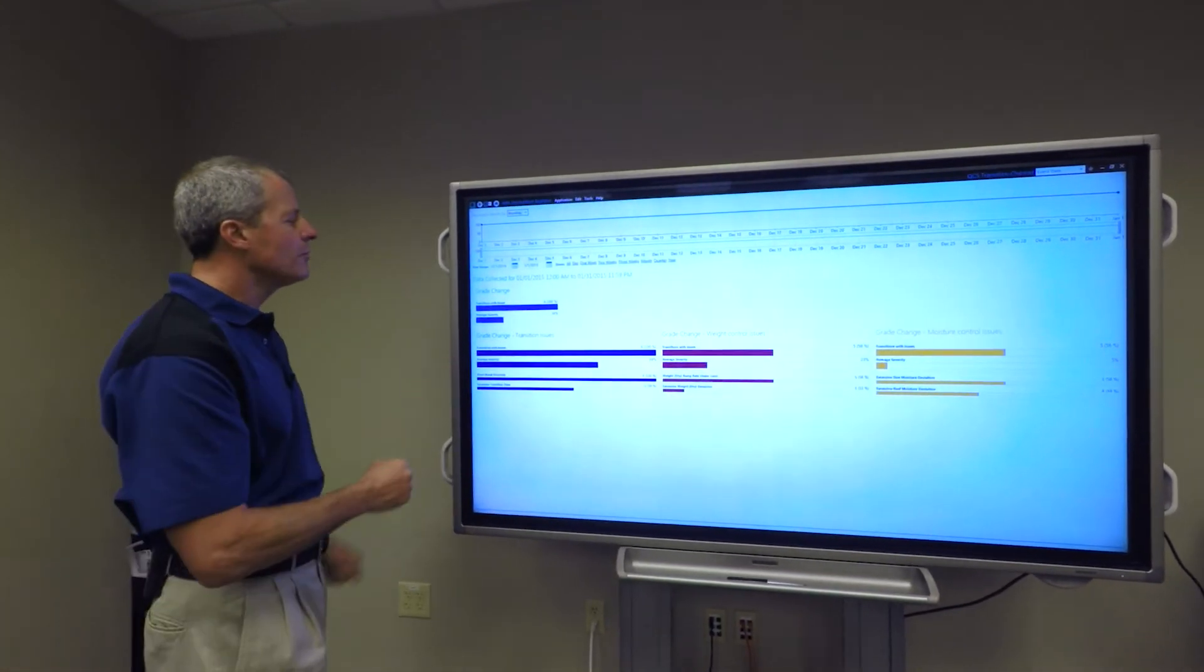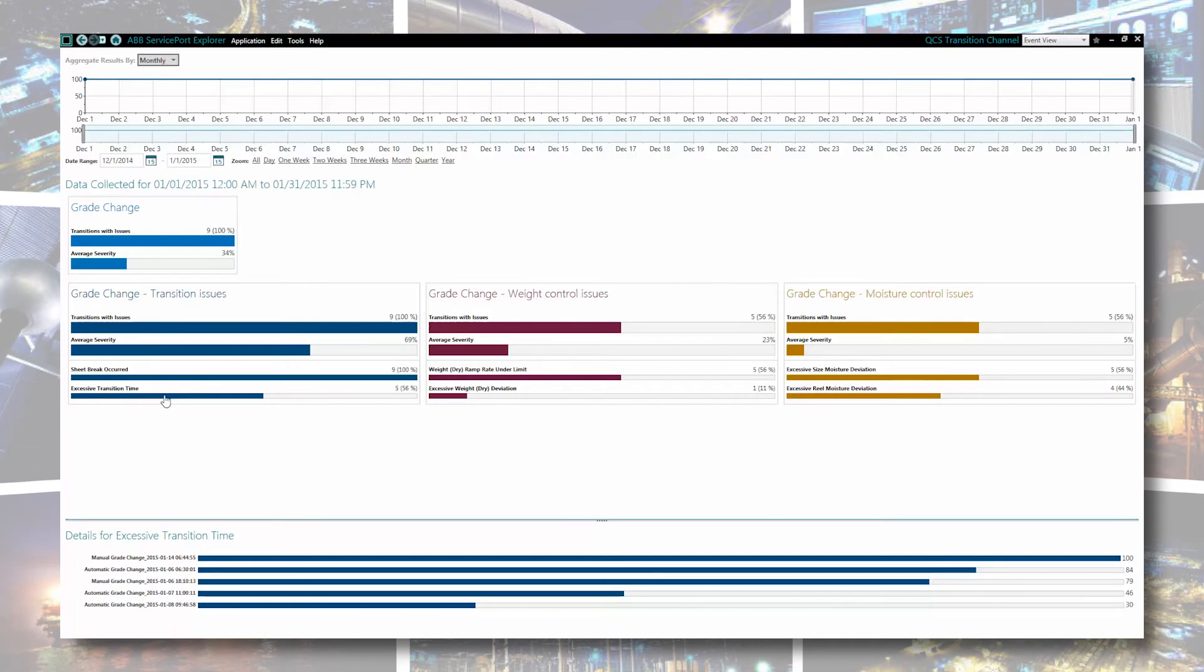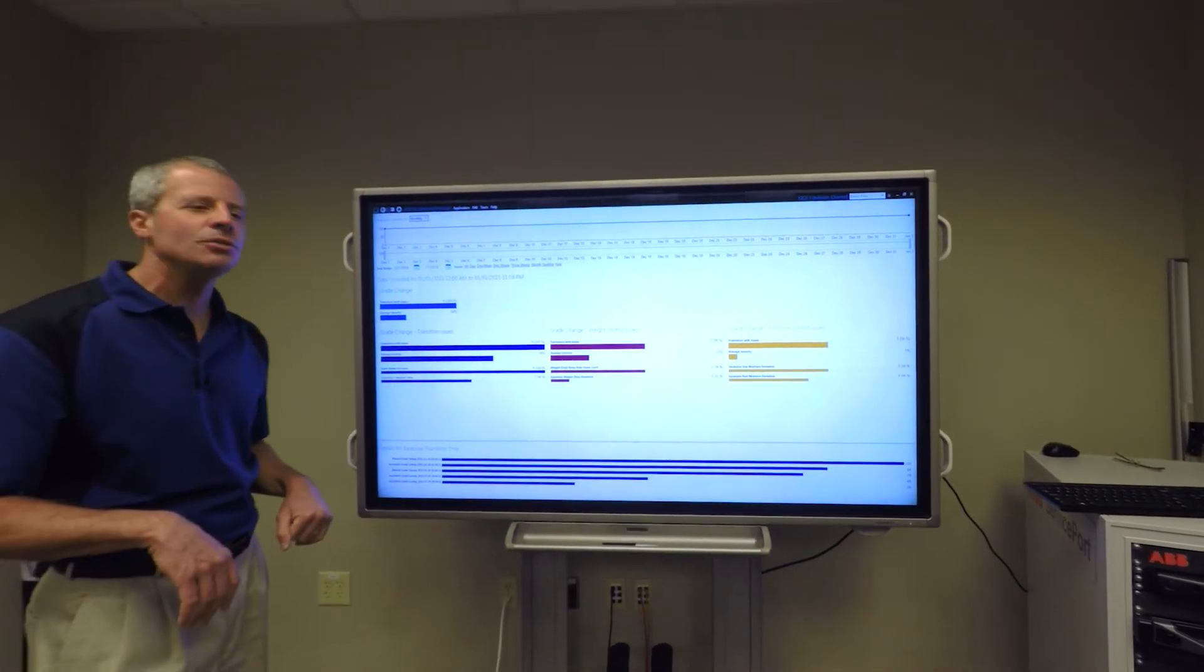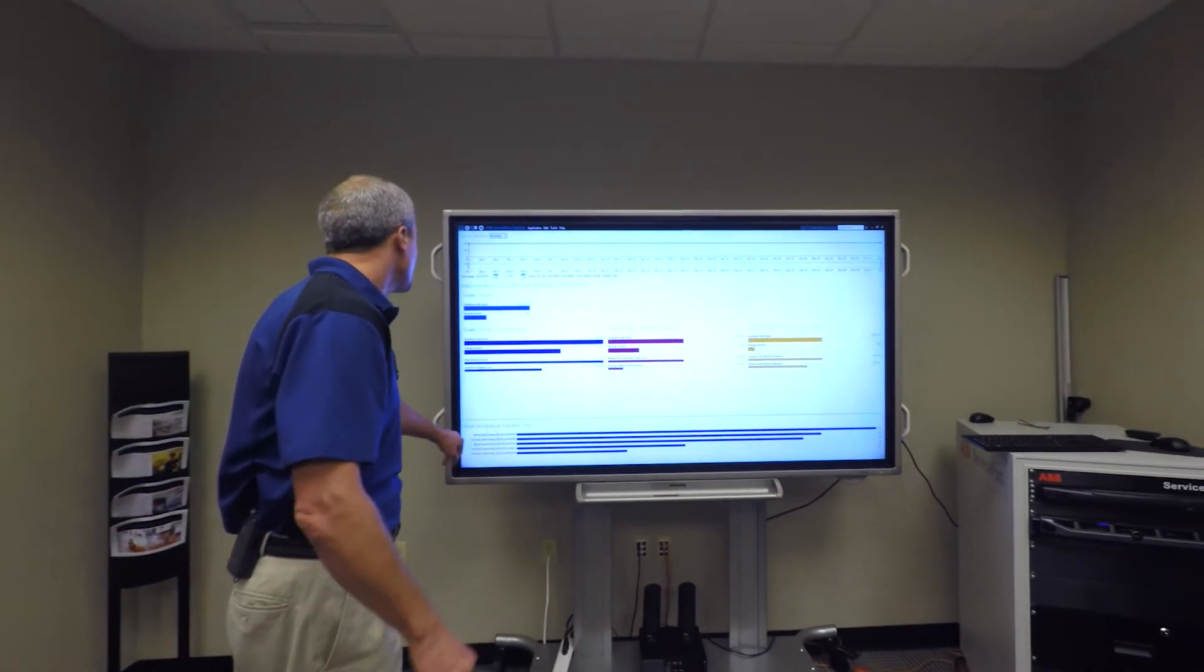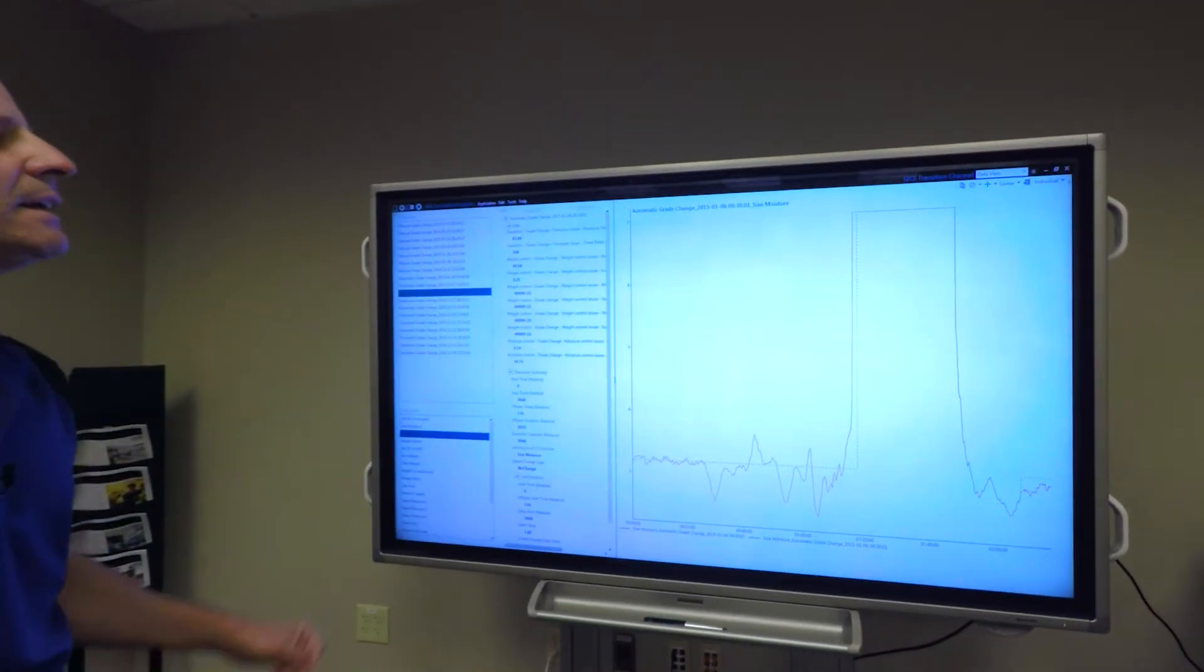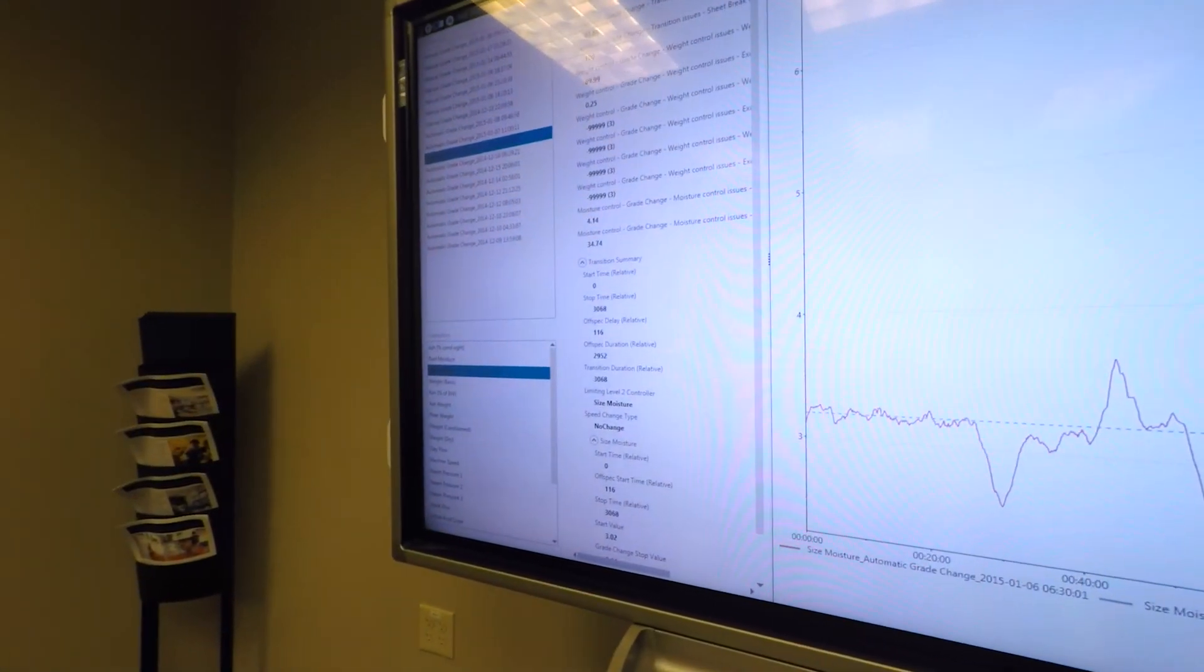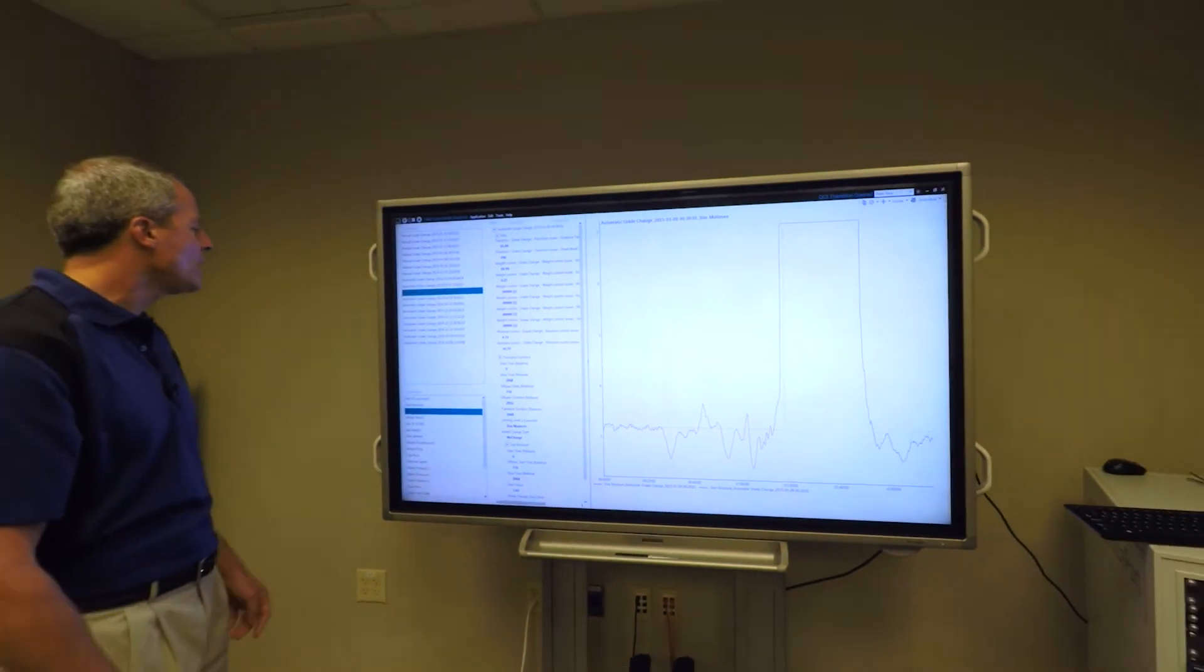Let's drive into one of these in more detail. On the excessive transition time, we can click here and see the list of transitions that each had a KPI. To refresh you on the KPI, a 100 means that's a pretty major issue versus a KPI closer to zero means we don't have an issue we really need to investigate. Let's pick one of the automatic grade changes. If we look at the automatic grade change and the data, we can look at the limiting level two control. This is the size moisture. The size moisture is what prevented this grade change time from reaching target as quickly as we wanted it to.